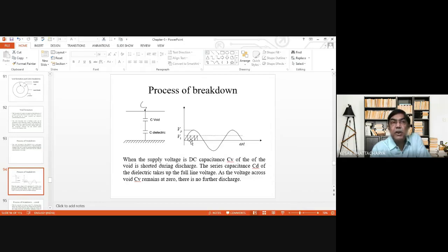Then, after some time, when the void regains its dielectric strength back, what happens? Once again, the stress may be such that it creates another breakdown. So this is what happens. A series of breakdowns may take place up to this point. A similar thing will occur in the negative half cycle also. So ultimately, in the long run, development of carbon particles due to heat generation inside the dielectric may be such that it may short circuit the core and the outer sheath, resulting in complete failure of the insulation of the cable.